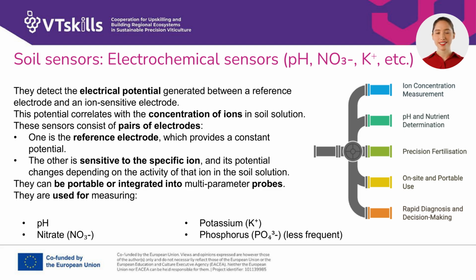These sensors consist of pairs of electrodes. One is the reference electrode, which provides a constant potential. The other is sensitive to the specific ion, and its potential changes depending on the activity of that ion in the soil solution. The potential difference between the 2 electrodes is proportional to the ion concentration according to the Nernst equation. It is used to measure pH, essential for nutrient availability.